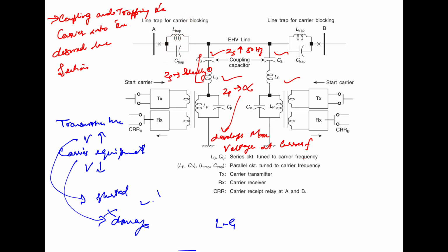For that, we have two line traps, which are parallel tuned LC circuits. These two line traps resonate at the carrier frequency, and they prevent the carrier signal from spreading into the rest of the transmission system by virtue of the extremely high impedance they provide at the carrier frequency. The line traps are designed so that they do not offer any significant impedance at 50 hertz, the power frequency. The line ends are thus clearly demarcated as far as the carrier signal is concerned, and this clear-cut demarcation helps in establishing a well-defined zone whose boundaries are crisply defined, which is good for the protection system.